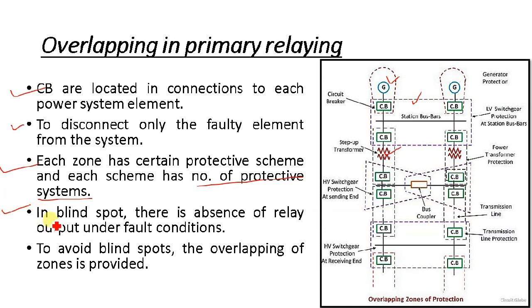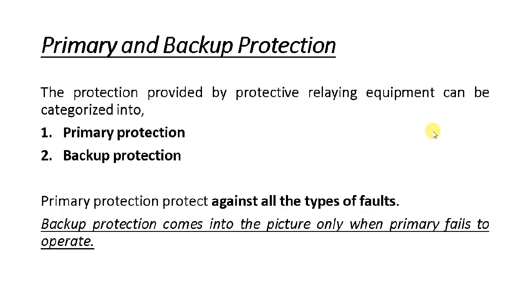When talking about the blind spot, there is an absence of relay output under the fault condition. To avoid blind spots, overlapping of zones is provided. When overlapping is done, the number of blind spots decreases. We can say that the protective zones are so designed that no area remains unprotected. When we decide on protective zones in a power system, our main criterion is that blind spots should be reduced for the complete protection of our power system.